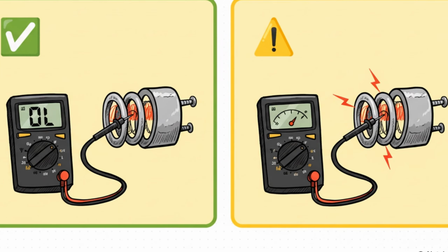Now, for the second and arguably more important safety test, put one probe on a heater terminal and the other probe right on the metal case of the heater. On this test, OL is what you want to see. That means there's no electricity leaking out. If you get any reading at all, even a flicker, it means there's a dangerous short. The element is leaking electricity and you've got to replace it immediately.